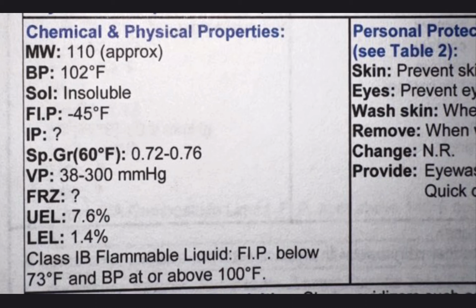It's because at 100%, you'll see triple X, meaning that you're in an explosive environment. And that triple X means that you've hit your 1.4%. And anything within this range for gasoline specifically, you know, different chemicals have higher ranges, that threshold is alarming. So since it's not linear, we don't know how many steps is difference between 10, 20, 100. It gives you a lower alarm at 10 and an upper alarm at 20 to build in those safety factors.